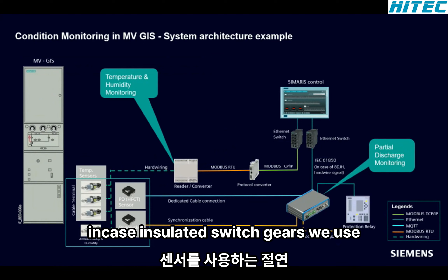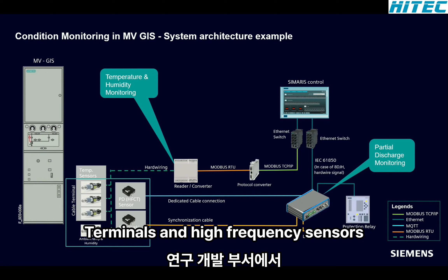In gas-insulated switchgears, we use temperature sensors in the cable terminals and high-frequency sensors together with a Rogowski coil for partial discharge monitoring. Here also the data from SIPROTEC relays is collected, and all the signals are evaluated by the Siemens engine to determine the health of the system.